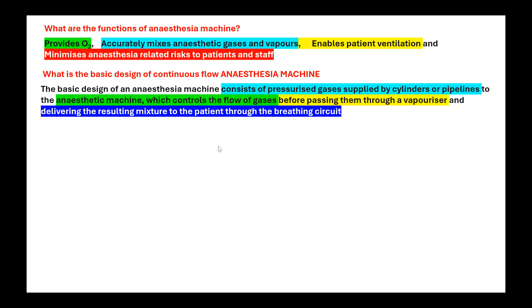So there should be four components. One is the gas source. Second is the control of flow by flow meter. Third is a vaporizer to mix the anesthetic vapor to the gas. And fourth is the breathing circuit to deliver that. So these are the four basic components of any anesthesia machine, whether your workstation or even better than that, if you deliver or create some newer machine also, these are the four components which are required. To understand that basic concept, you will be able to understand whatever sophistication the machines are made into.